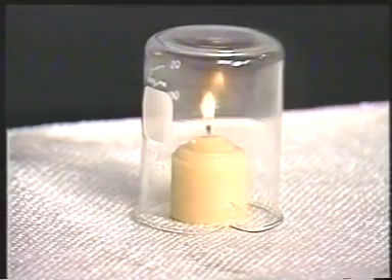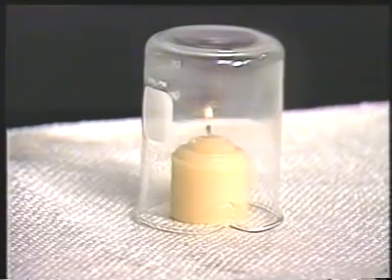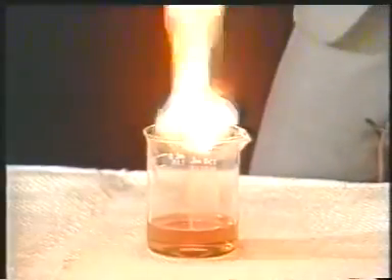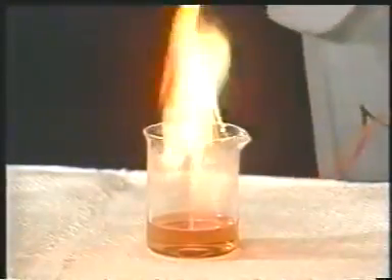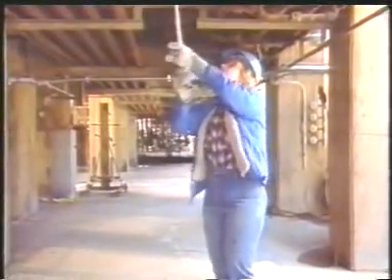Air is needed for combustion because it provides oxygen that reacts with the fuel. The final thing needed for combustion is a source of ignition. The ignition source provides the heat energy that is required to start the combustion reaction. In the operation of a fired heater, it's important to maintain the right proportion of fuel to air. When this is done properly, combustion will be complete and the maximum amount of heat will be generated without any fuel waste.